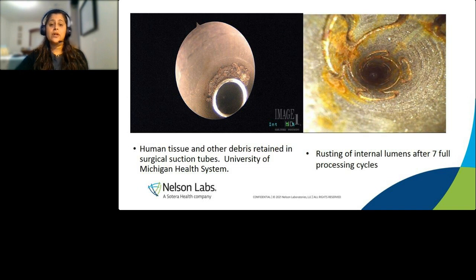This picture on the right, where you see the rust happening, this is only after 6 reprocessing cycles. So thus, the FDA's concern was valid to perform reusable cycles before you do the cleaning validation. And we saw this just after 6 cycles. And this is very alarming because things were flaking off from the inside. So the outside was perfectly fine, looked polished, looked very well.